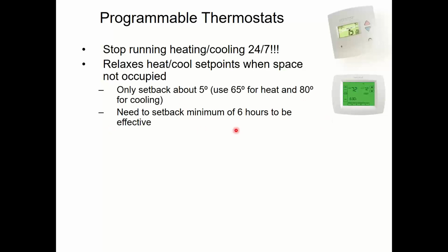Will it save energy if you only do it for 2 hours? Sure. It's just that at some point, the effort for me to program these things compared to the amount of money I'm going to save, to let it go in the setback for 2 hours is kind of wimpy. 6 hours is kind of the minimum. Most buildings can do more. If your building's occupied from 7 a.m. to 5 p.m., what is that, 10 hours? That gives you 14 hours of setback you can do. So most buildings can do way more than this. This is kind of like the minimum effort to put in here.